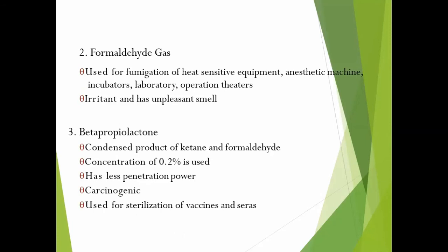Number 2 is formaldehyde gas. Formaldehyde gas is used for fumigation of heat-sensitive equipment, anesthetic machines, incubators, laboratories, and operation theaters. It is irritant and has an unpleasant smell.